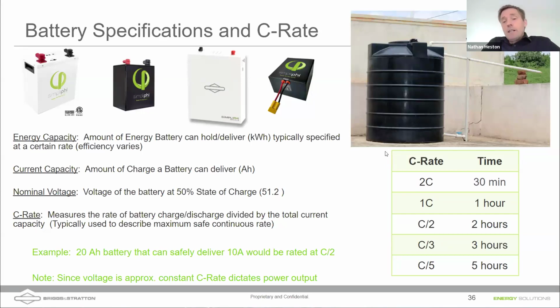To give you an idea, a lithium iron phosphate 48 volt battery is about 50 volts. If I'm running 100 amps through it, which is what the breaker on our batteries are, that's 5,000 watts. So the batteries can generally surge at that rate, but you wouldn't want to do that full for 1-2 hours straight. A battery that'll safely charge and discharge in 2 hours is rated at C/2.